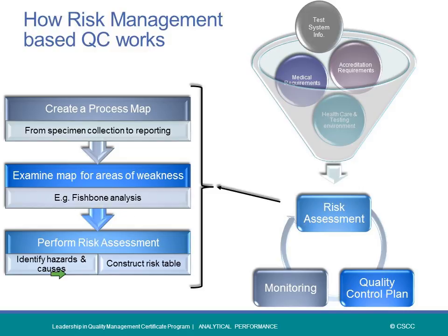occur or defects could occur, then construct a control plan that would not only address the analytical phase, but also address maybe pre-analytical factors, factors related to maintenance of the instrument, and maybe manually checking optics every now and then if this is not done automatically in some way by the manufacturer itself. By doing so, of course, we improve the entire analytical process, and hopefully with the outcome of reducing medical error.